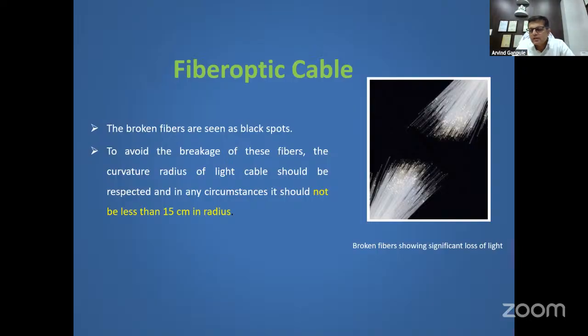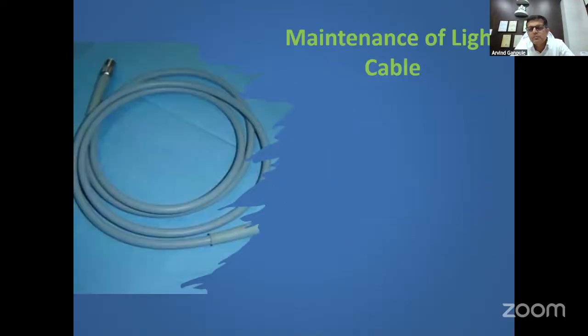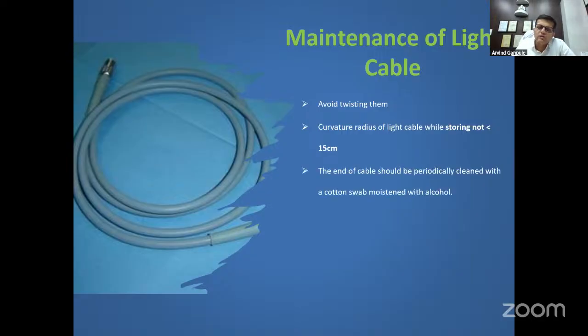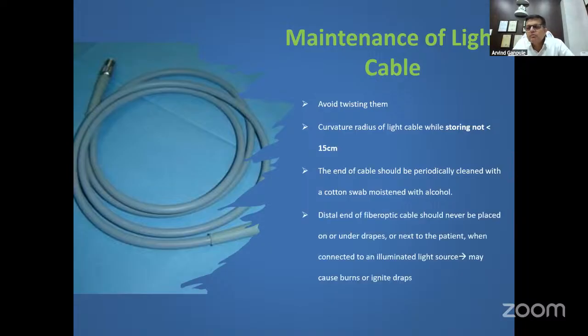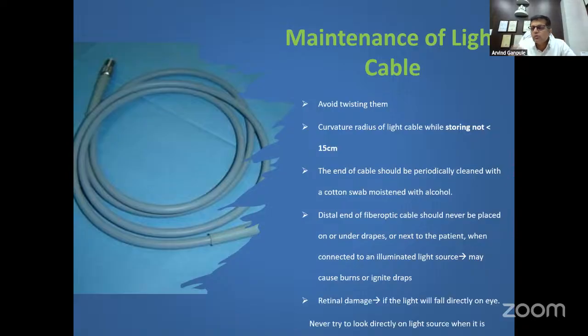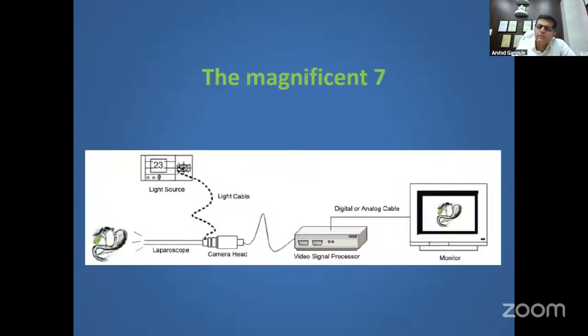And for preventing this particular problem, although it will not be completely prevented, there are a few important things you have to remember. Avoid twisting these cables. The curvature radius of the light cable while storing should not be less than 15 centimeter. The end of the cable should be periodically cleaned. The distal end of the fiber optic cable should never be placed on or under drapes, as I just mentioned, that they tend to cause burns or ignite drapes. Never hold it against the eye of somebody, because they tend to cause retinal damage as well.